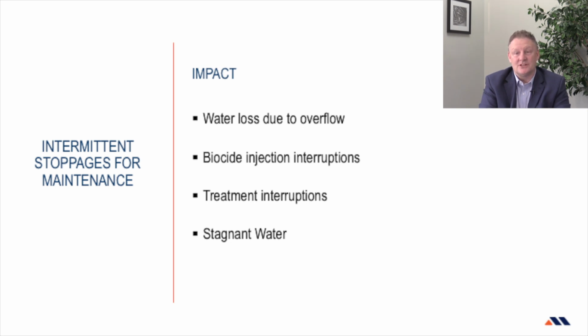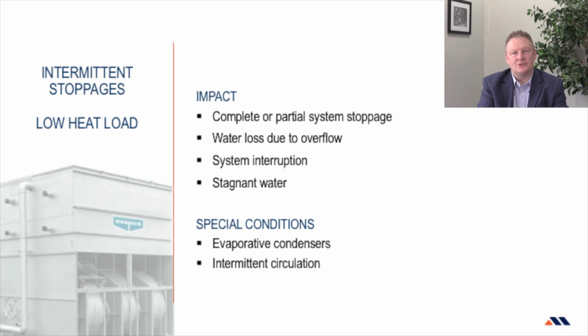If the stoppage is longer than 2 to 3 days, the stagnant water will increase the risk of microbiological growth as it is the perfect condition for bacterial proliferation. Unfortunately, we cannot plan intermittent stoppages for low heat loads as they depend on the system's requirements as well as the outside temperature. It's difficult to prevent problems associated with these interruptions. In these situations, the disadvantages will be the same as those as unscheduled stops for maintenance.